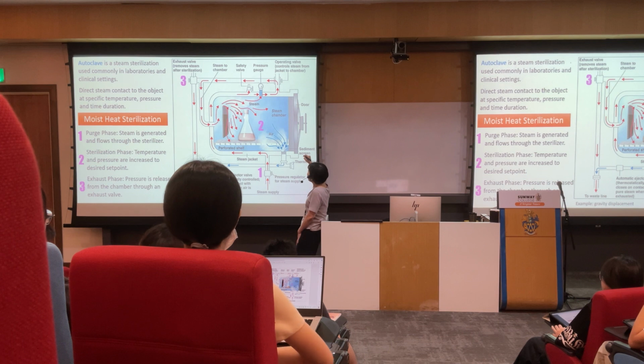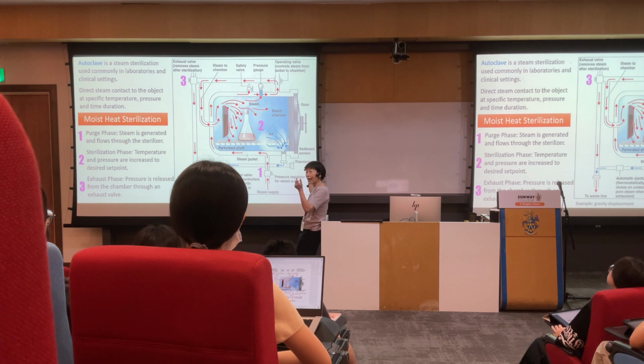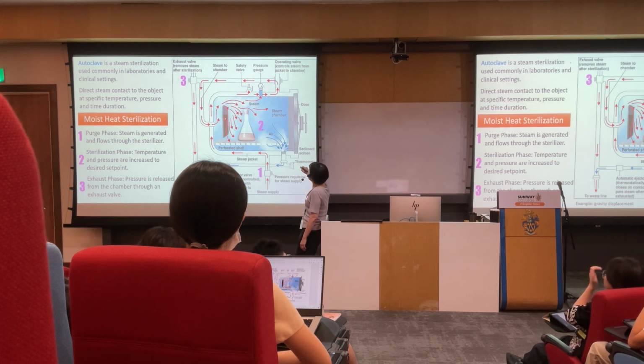What happens is that you will have the objects. Let's say that you want to sterilize the medium. You have a flask and a cap, but normally the cap is not tightly capped, it is very loosely capped, because you cannot just screw it tight. Even when you use a screw cap, you need to turn it loosely. You need to allow the steam to go in, because you want to sterilize the medium. You need to let the steam get in contact with the medium, so that the heat reaches the medium and kills whatever bacteria are in it. So you need to have the cap loosely on the flask. And this is how you do it.